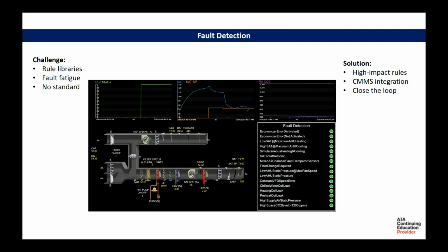Going to the slide on screen, it's a standard air handling unit. There are definitely many hundred rules we could find in different libraries online, but there's really only 20 or 25 that are truly valuable and that you would want continuously running on your equipment. An obvious one is the economizer. Everybody should be looking at the operation of economizers, because if an economizer gets stuck open in summertime, number one, it's very expensive, but number two, the chiller and the capacity of the coils aren't designed to cool air at the summer design point at 100% outside air. So it's just going to be very uncomfortable in your buildings.